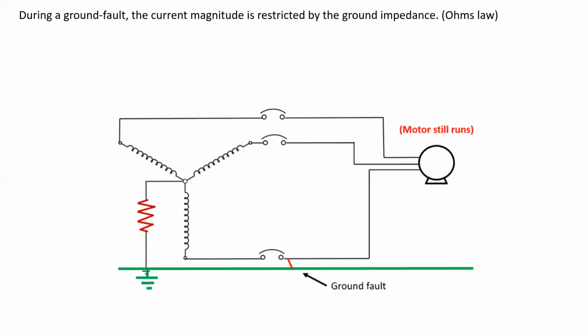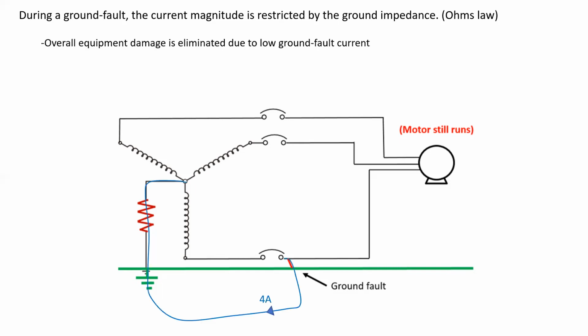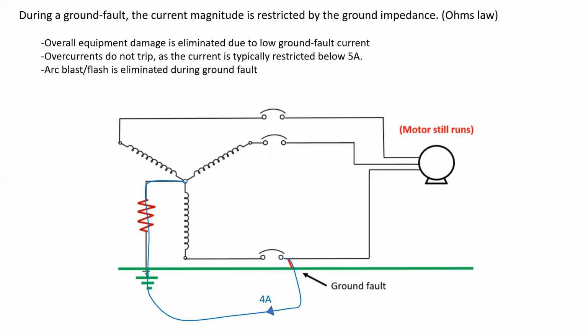During a ground fault, the current magnitude is restricted by the ground impedance, and that's because of Ohm's law. The overall equipment damage is eliminated due to low ground fault current. The overcurrents do not trip, as the current is typically restricted below 5 amps. Any arc blast or flash is eliminated during the ground fault event. All this looking pretty good. The voltages remain stable, and it provides protection for generators.